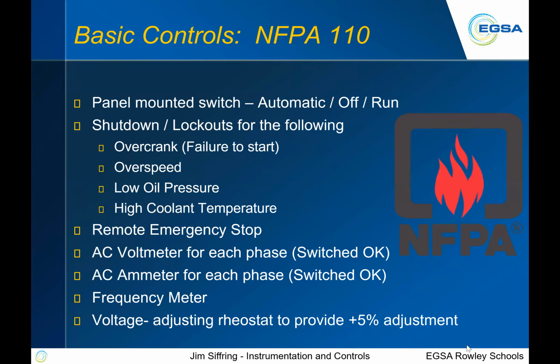Okay, so now we've gotten all this. What are we going to do with all this instrumentation? NFPA 110 is the guiding NFPA standard, pretty much the basic standard for all building type stationary standby emergency generator sets. NFPA 99, of course, goes to medical facilities and refers back to NFPA 110 as well. But pretty much NFPA 110 is the basic standard we have to work with. So what do we need to satisfy the requirements of NFPA 110 for instrumentation on a genset?